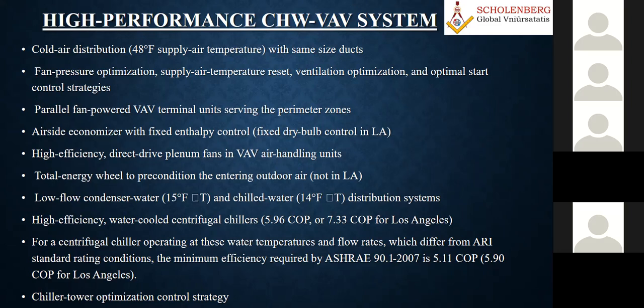Water can be air cooled or water cooled, and depending upon that, even the supply temperature, as majority of the time we design this load for a peak load condition. So you also have to have a proper part load operating condition design. And in selection itself, you should go for high efficiency chillers. Depending upon the place, a lot of research reports are available in ASHRAE from the US, from California actually, because in Texas and Arizona they normally do a lot of cooling.